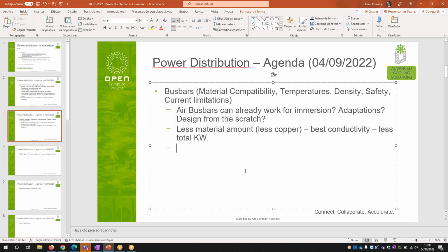In this application, the bus bar is immersed in the fluid, lying horizontal in the tank. There are a lot of different solutions in the marketplace right now, and what we're discussing in this group is a tank-based solution where all the servers, and therefore the rack's power, are in the tank since it has to reach all the servers. There are other applications where that bus bar equipment stays external to the tank or the immersion fluid, which are your normal air-cooled solutions.